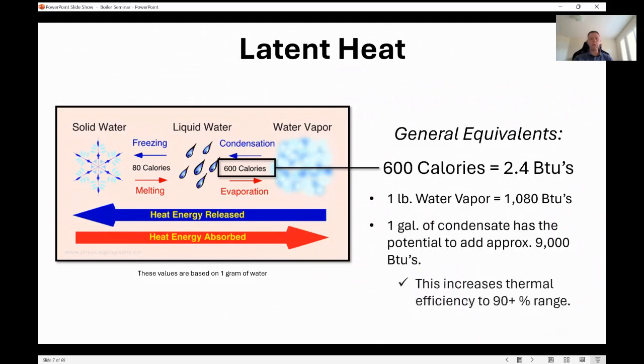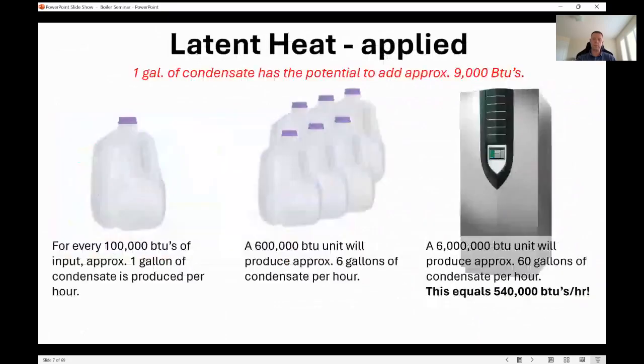So roughly 1 pound of water vapor is going to give you about 1,000 BTUs. So put that into gallons of condensate, which I think makes a lot more sense to all of us. 1 gallon of condensate is going to produce approximately 9,000 BTUs. And that's how you're going to get, by condensing this water vapor, that extra energy. That's where you're getting above that 90% efficient range.